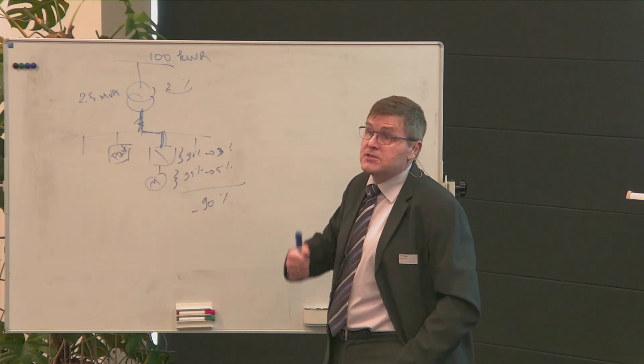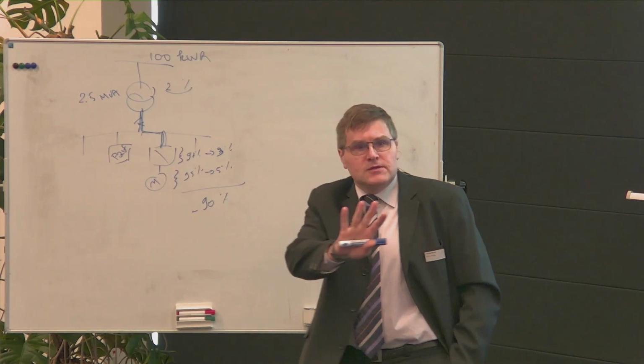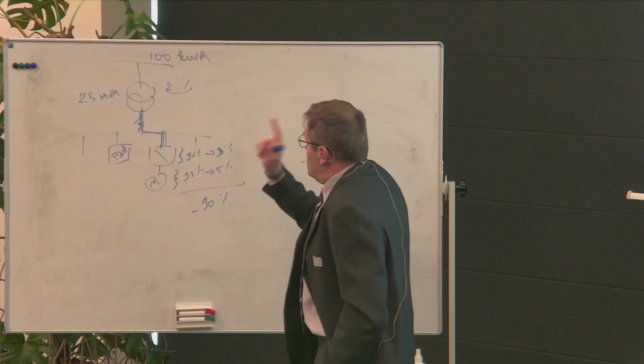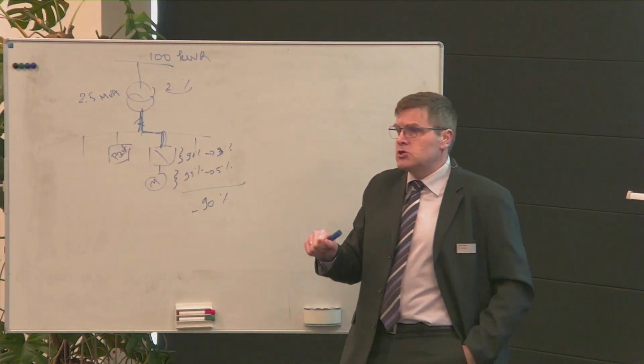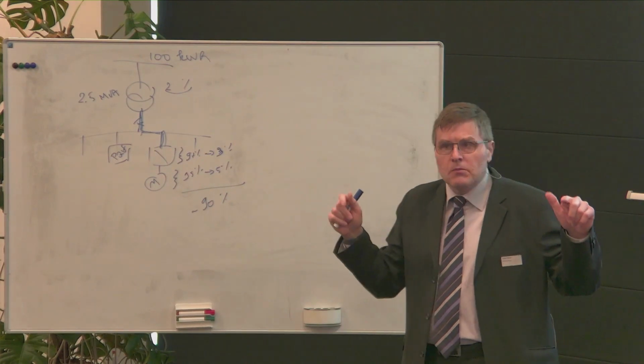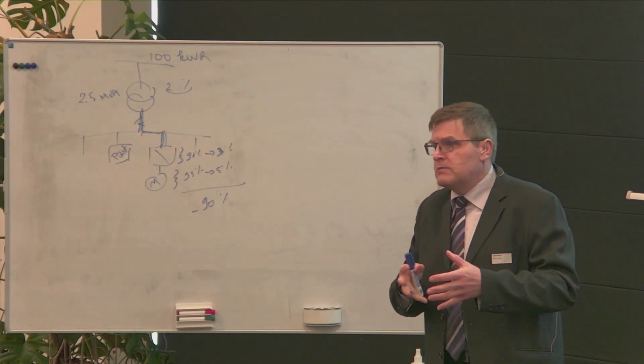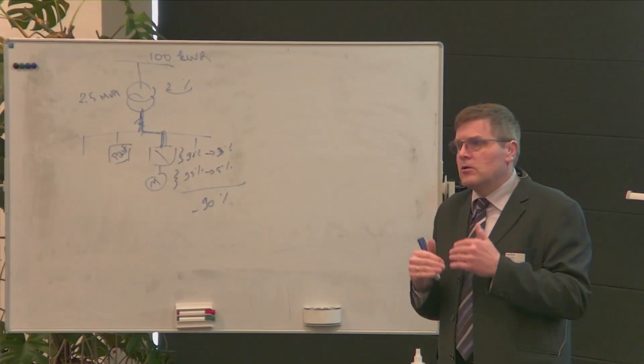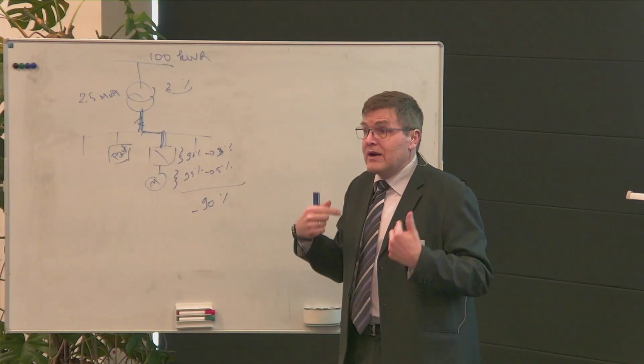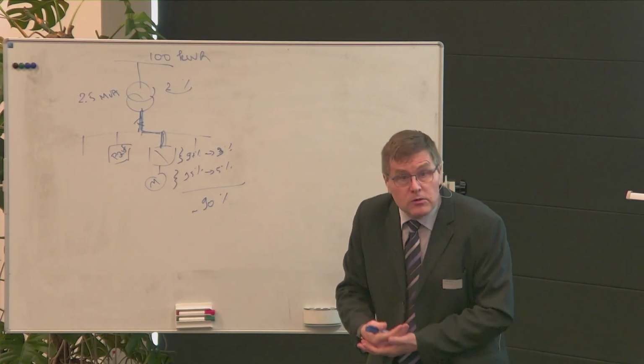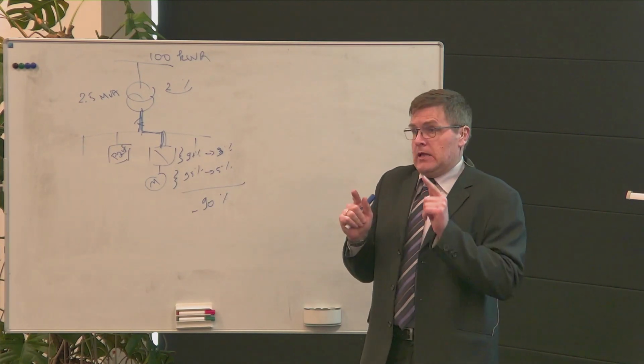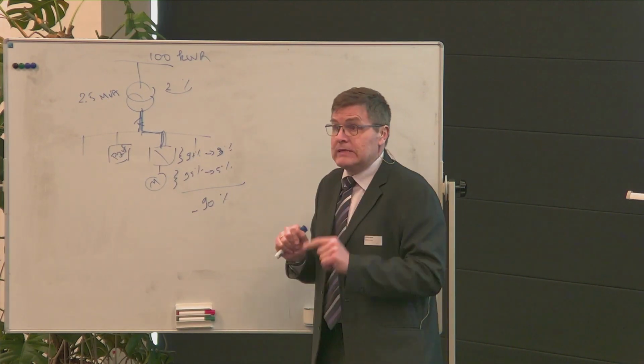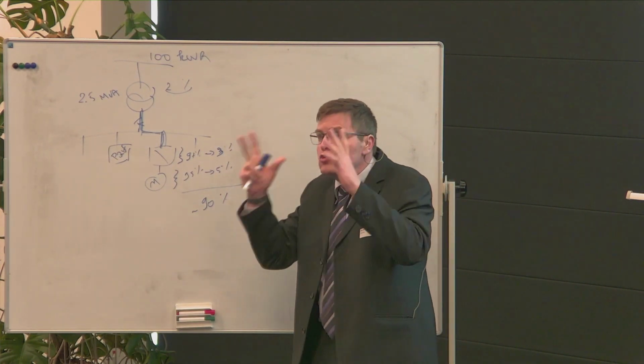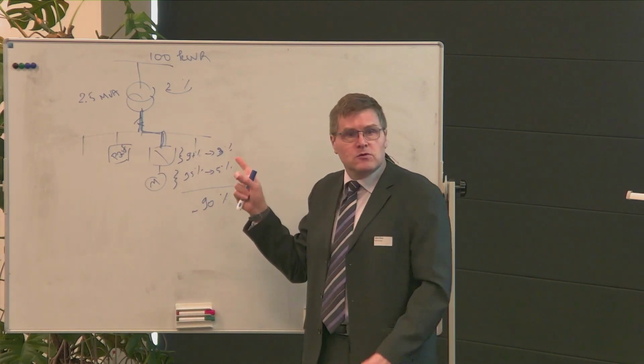We told the customer that it was a test, so we would disconnect the filter and bring it back. But no, said the customer, I want to keep it, because before, when I was running my installation above 80% of the load, all my machines were vibrating. You see the harmonics. I started to have misfiring in my PLC, so I could never go above 80% of the load of the transformer. Otherwise, I have technical issues. Now I can work at 100%, no sound, no problem. And instead of making the quantity of bread in 8 hours, I just need 7 hours. It is a huge improvement for me because of night workers, so I can reduce my team.